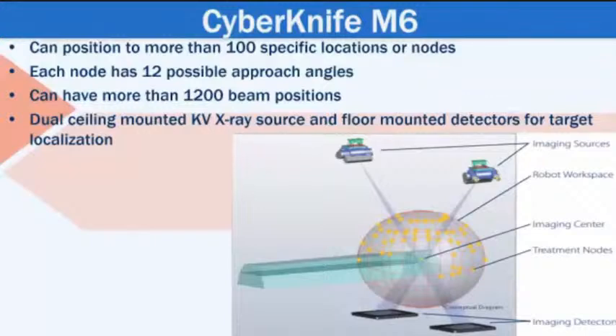The CyberKnife delivery system uses kV X-ray imaging to check the targets throughout the treatment. The imaging system consists of 2 ceiling-mounted X-ray sources and 2 corresponding in-floor image detectors. Live digitized X-ray images are compared with DRRs from the treatment plan.